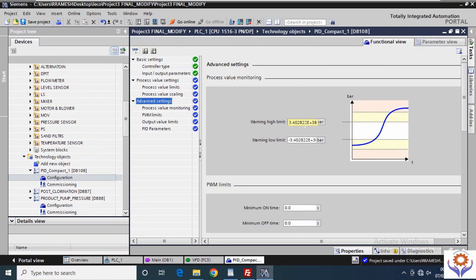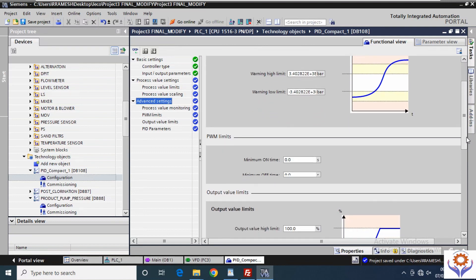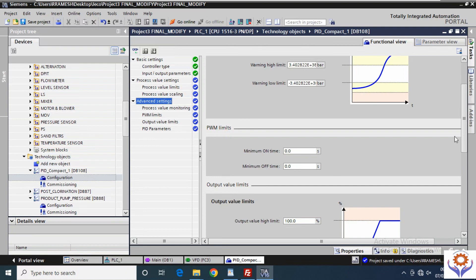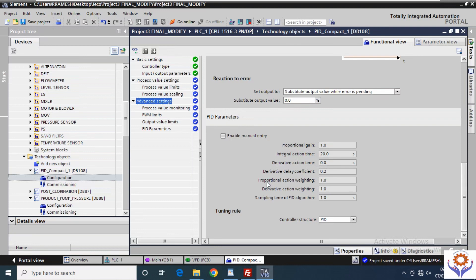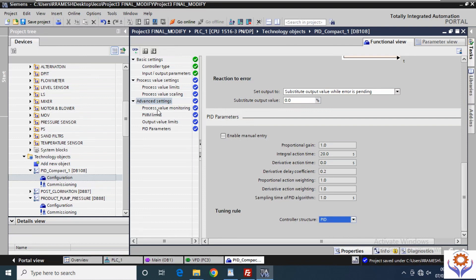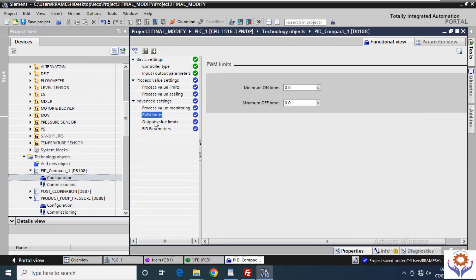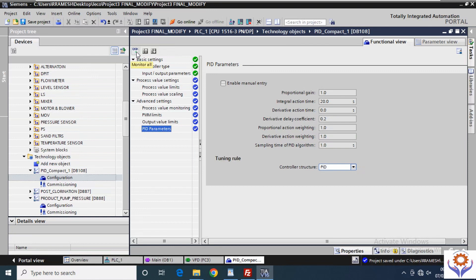You also have process monitoring limits, output value limits, and PID parameters. Each function has subdivisions. For example, Output Value Limit already has default values — it's better not to change them unless required. For PID Parameters, you can view and edit the values: default proportional gain is 1, integral action is 20, derivative action is 0, delay coefficient is 0.2. The controller structure can be set to PID or PI only, based on your requirement.